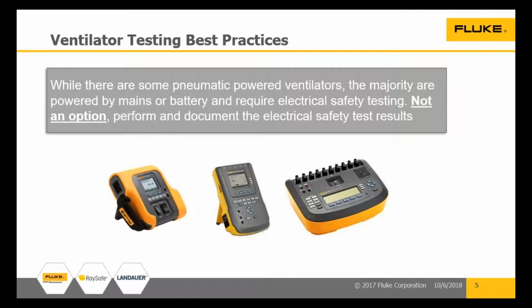All right. Now here's the problem. Even NFPA 99 says you must do what they're now also calling touch current test, and that is the old enclosure or chassis leakage test. So here's what that test says. And I'm going to draw from the international standards also, because NFPA 99 somehow tends to not be very specific about these things. The touch current test is supposed to be done to a test point near where the patient or a caregiver could touch the device and touch the patient at the same time.